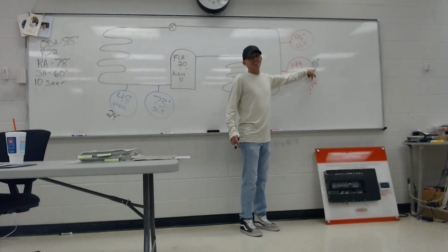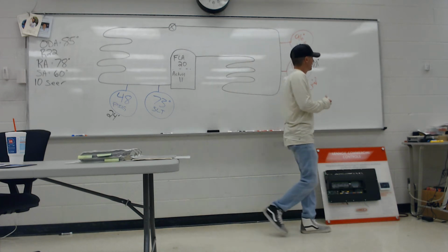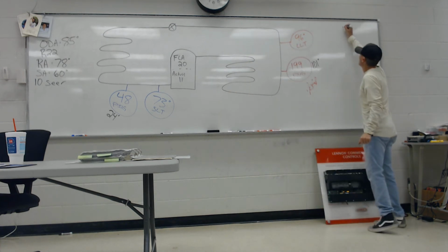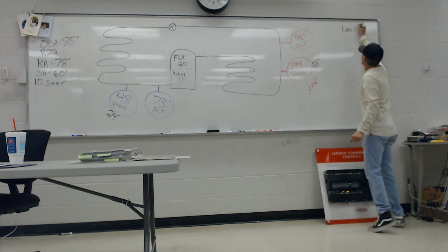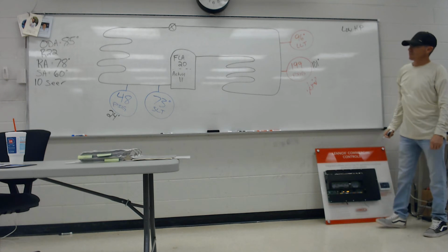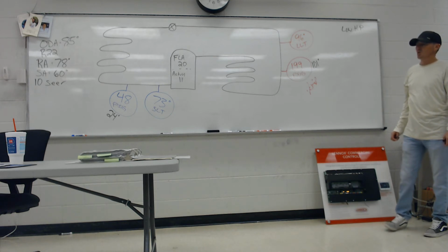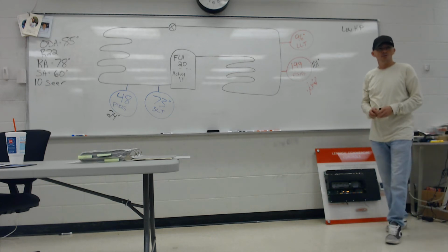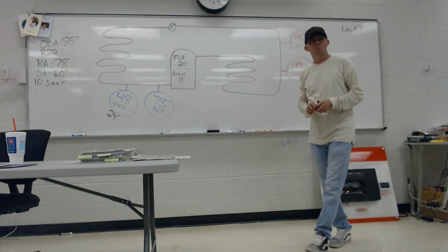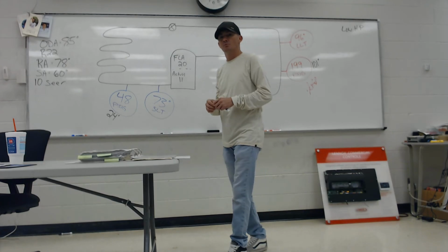No. So what can we say about our head pressure? Low. So I start checking this stuff off: I've got low head pressure. And I've already been inside and taken a reading, dry bulb only, just keeping it simple. Evaporator TD. What should my evaporator TD be? 30.